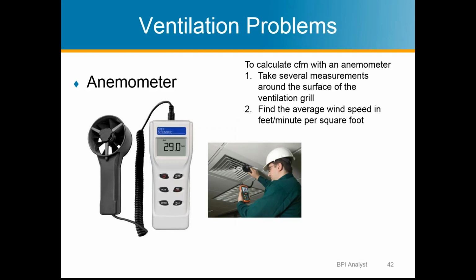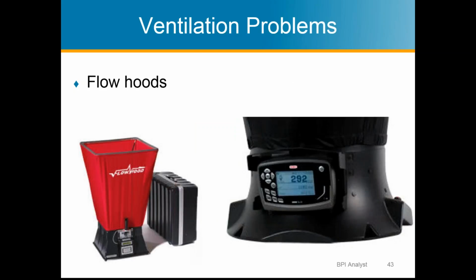An anemometer can also be used. Here he's measuring a supply or return in a commercial building, but it basically just measures air speed, and with some calculations can give you an approximation of the CFM that's leaving. And then flow hoods. Again, the best application for them is to measure return air from an HVAC, not from ventilation systems, specifically residential systems where the flow is low.